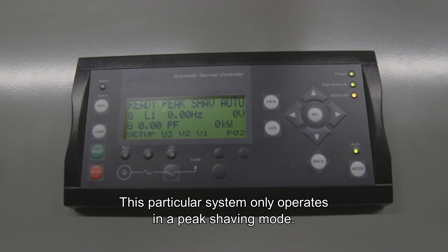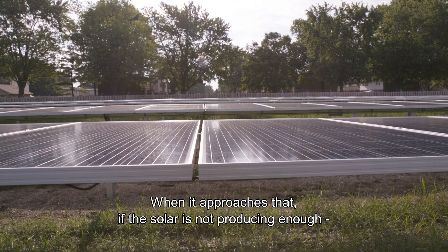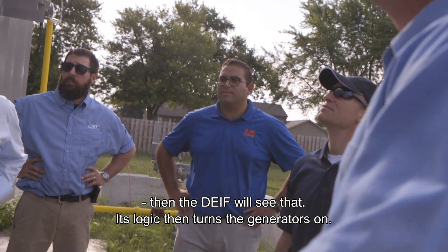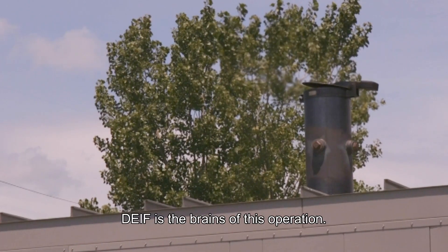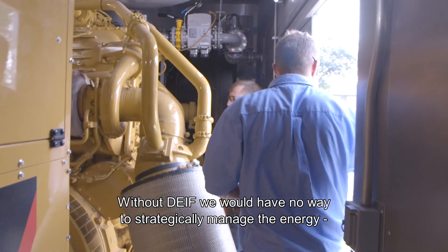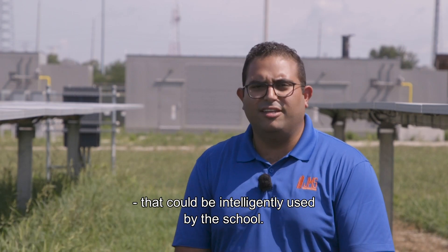This particular system only operates in a peak shaving mode, meaning it looks at a set point of power that the school wants to use from the utility. When it approaches that set point, if the solar is not producing enough, the DEIF system sees that and its logic turns the generators on. DEIF is the brains of this operation — without DEIF we would have no way to strategically manage the energy and demand output being created on site and intelligently used by the school.